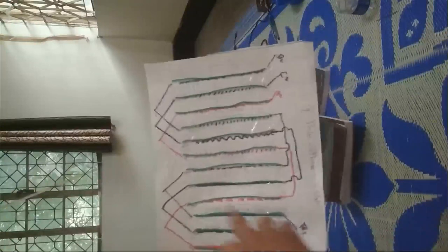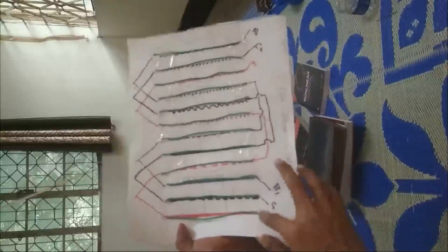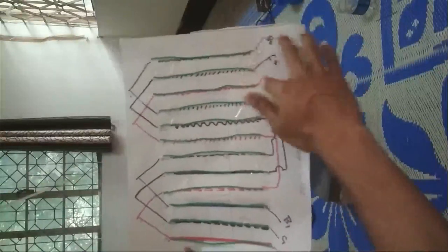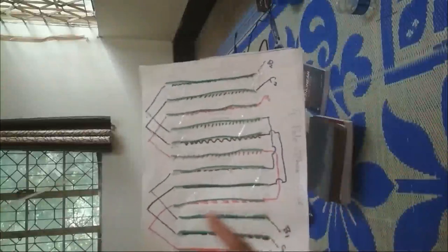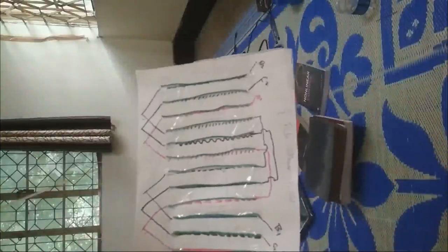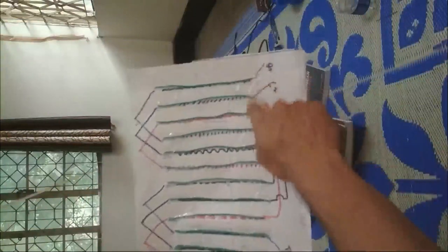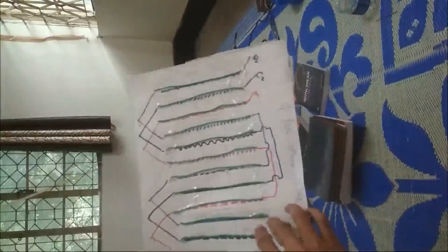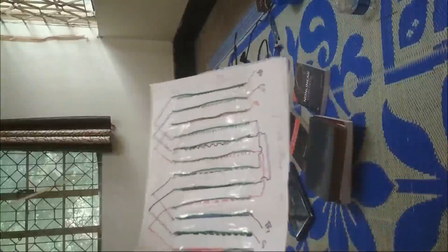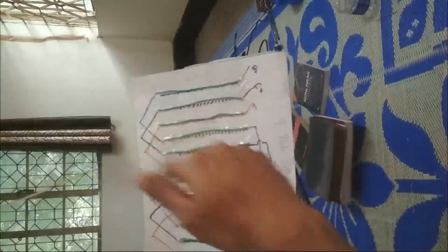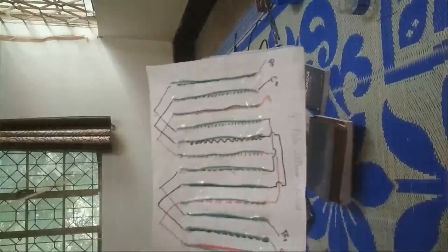Now similarly you connect B in series, C in series. Once you have taken this A1, B1, C1, and here you have A2, B2, C2, you can connect them like a three-phase transformer. There is no other magic. If you short one end and use these terminals as your either output or input terminal, then it will form a star. Or you can connect A1 with B2, C1 with A2, and B1 with C2 to form a delta.